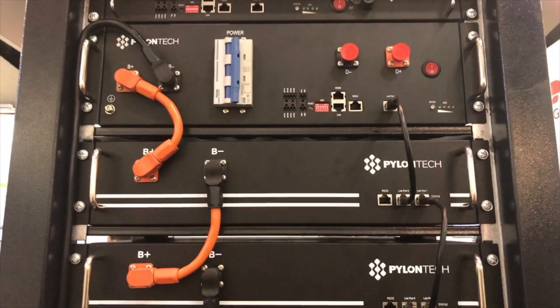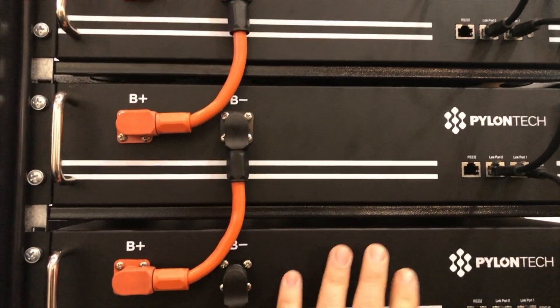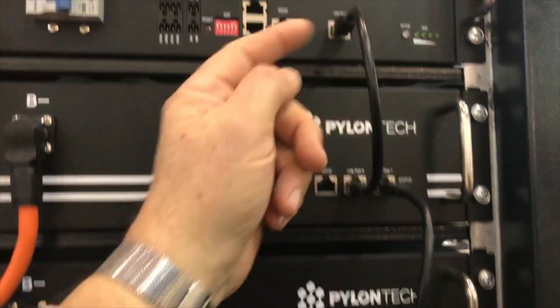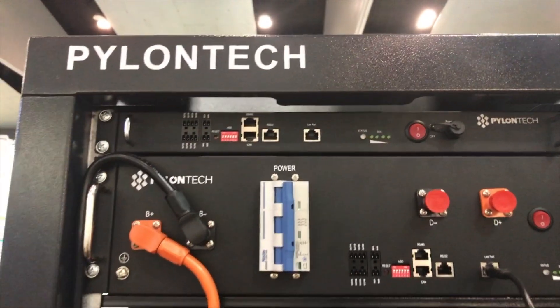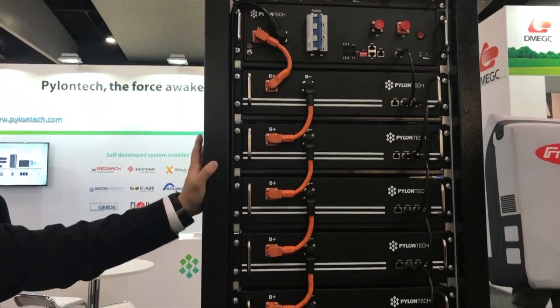So you've got multiple levels of safety. Built into each battery unit is its own BMU, and the BMUs are collectively chained through communication cable to a BMS, with a communication unit at the top. The whole stack capacity is about 33 kilowatt hours. We also have another module — it's much bigger and higher density.